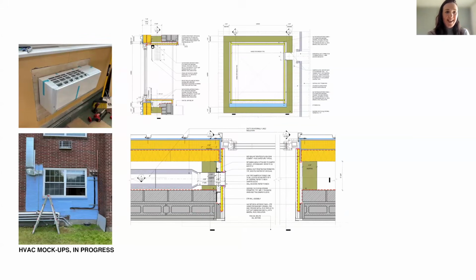And so we've done a lot of mock-ups. I'll say the unit installed in this top left photo is the correct unit, it's just not the correct location. But we basically have been chipping away at mock-ups to make sure we've got everything just right. I mentioned this is a code conundrum. There's a lot of really interesting things going on here that we could talk about for a long time, but the gist of it is a 2-hour fire barrier is necessary between the brick and the new panel. It's essentially acting like a curtain wall, right? So every opening we have, every window, anything that penetrates both layers, our existing and our new, we need to have a 2-hour fire barrier there.